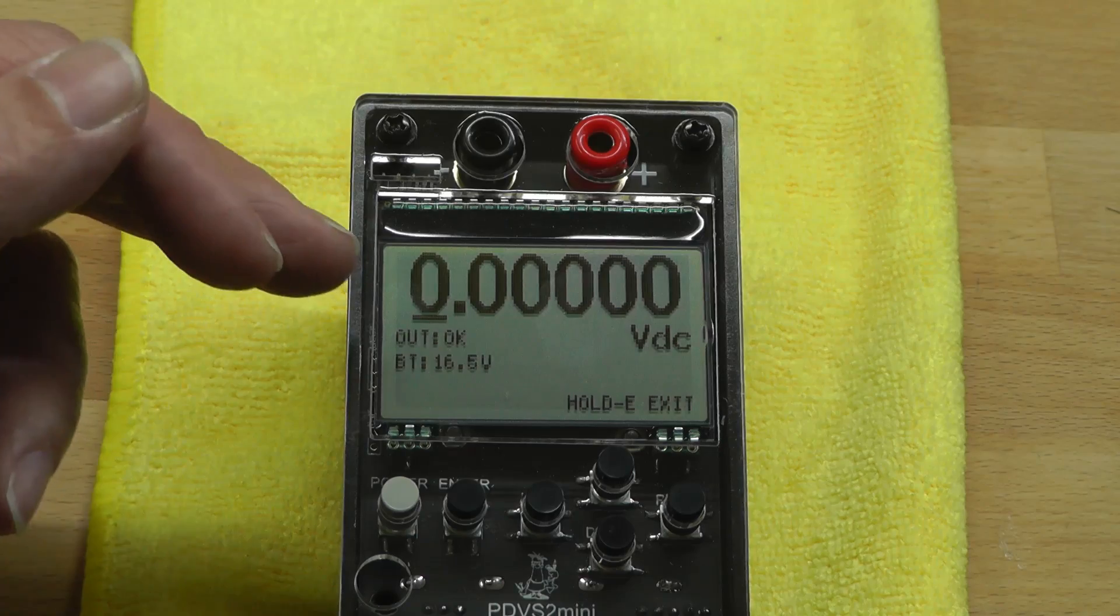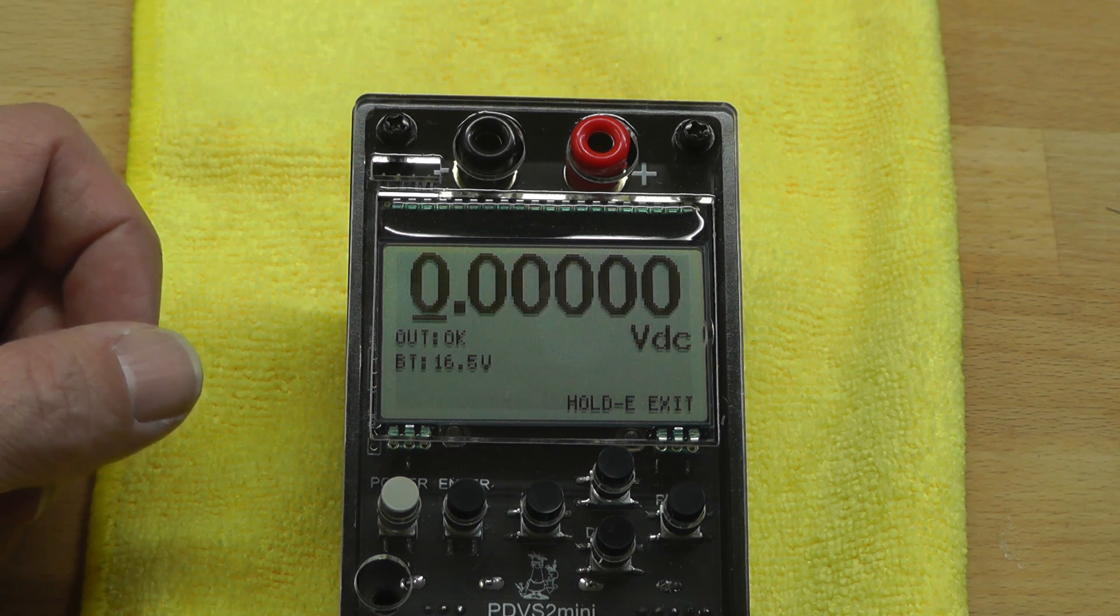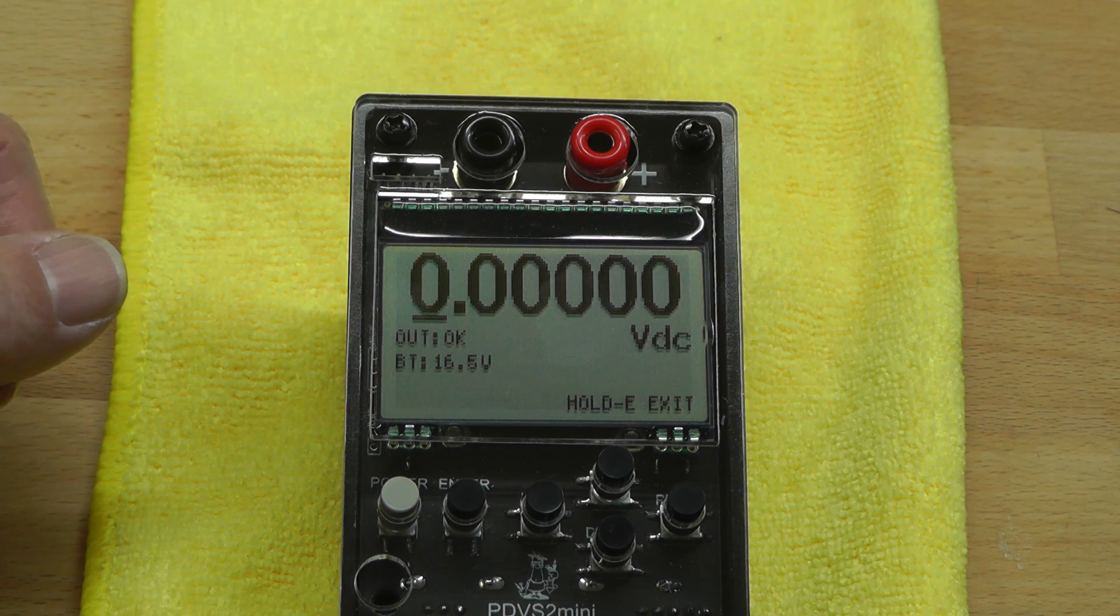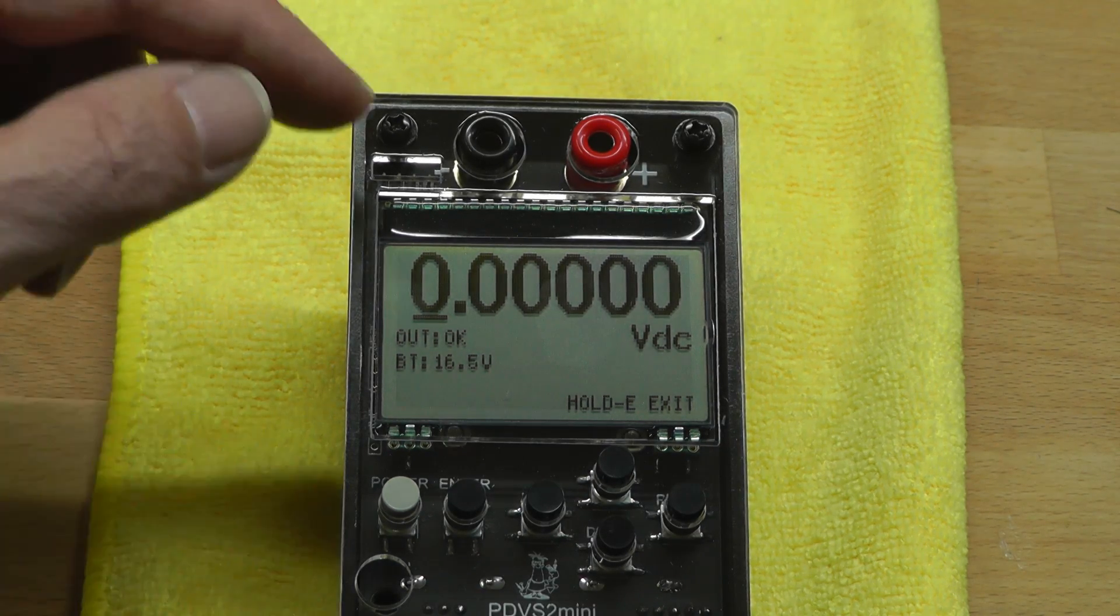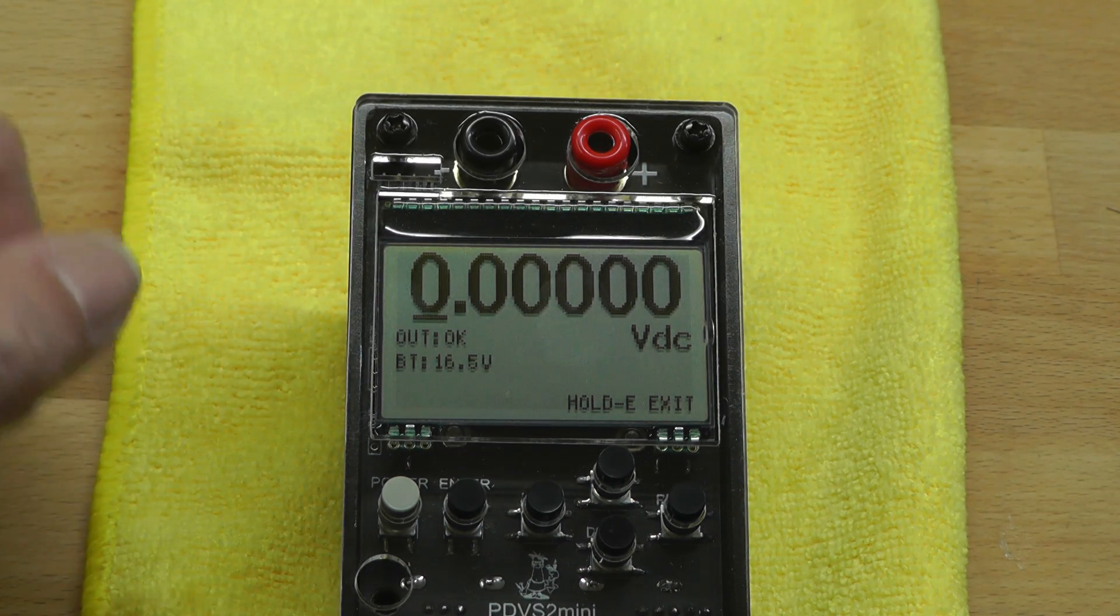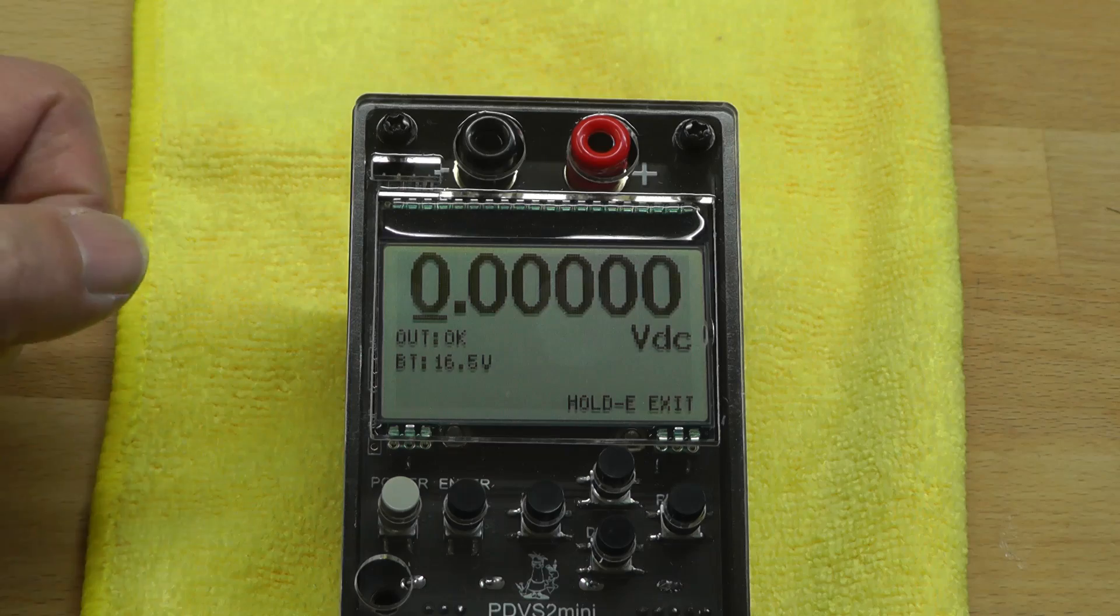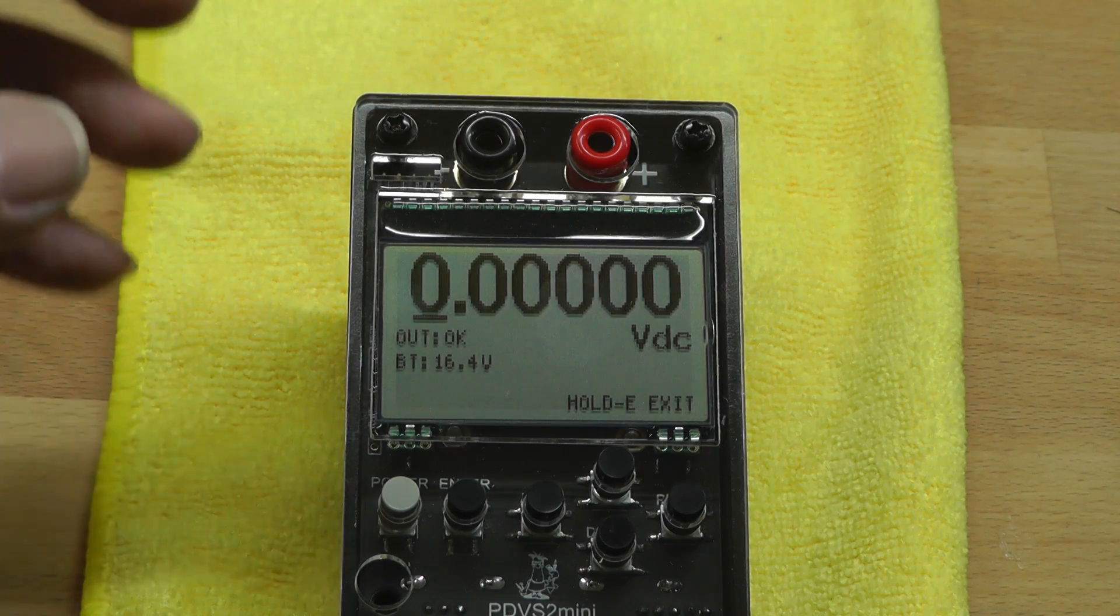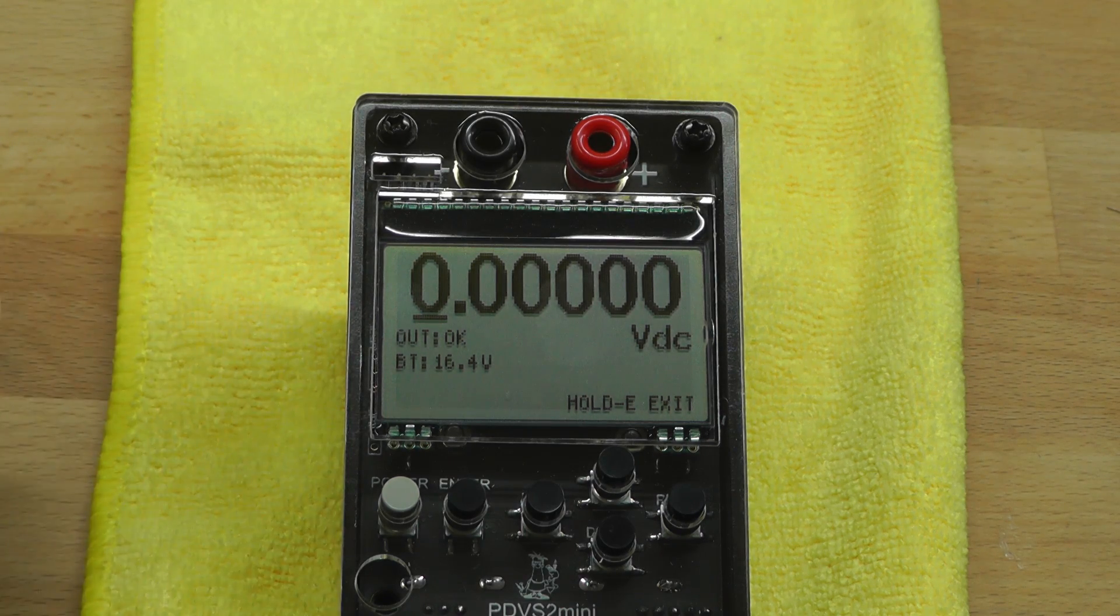And when you've got a batch of 50 PDV-S2 minis to do it takes a long time to go through that process and I often wondered if there was any way I could automate that. Now the PDV-S2 mini does have a serial interface that connects to the PC and I've got a VB app that I've written that I supply with the PDV-S2 minis in order to remote control the PDV-S2 mini - i.e. you can control the output voltage here. And I thought, well that means I've got control of the PDV-S2 mini from the PC. What I need is control of the multimeter from the PC as well and I can form a control loop.